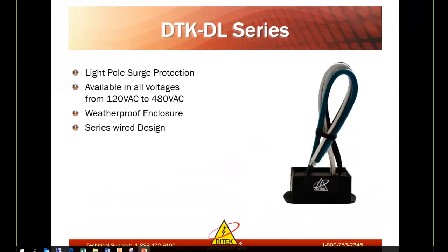The DTK-DL Series is a series device. It is 30 amp rated. It's a light pole protector. It's completely encapsulated. We offer it in basically 5 different voltage configurations ranging from 120 to 480. It's in a waterproof enclosure. It's got that very large number 6 gauge ground wire. So it's there to protect for parking lot lighting, street light, highway lighting. It's to provide protection for the ballast or the LED driver.